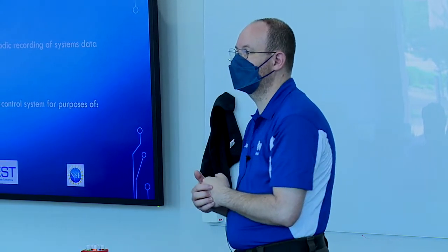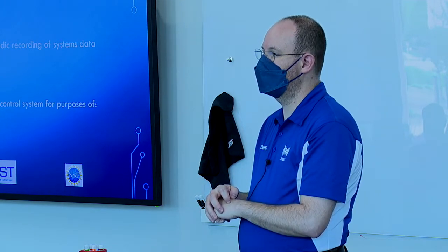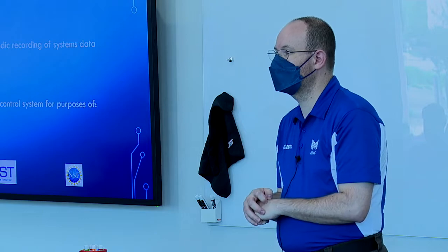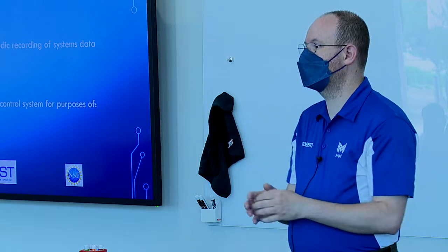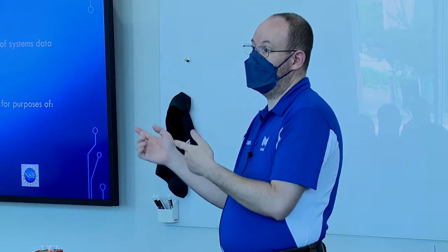I've been in the commissioning field for 15 years, and I tell you, the problem normally is everybody runs to the alarms. Alarms just tell you you have a problem. The logs tell you how to solve the problem. What caused the problem, how to solve it, so how to avoid it next time, sometimes.